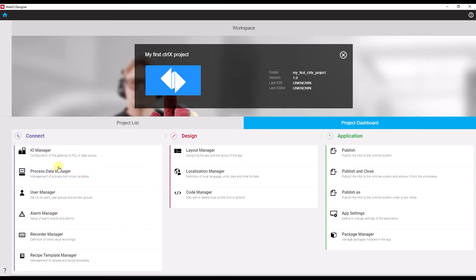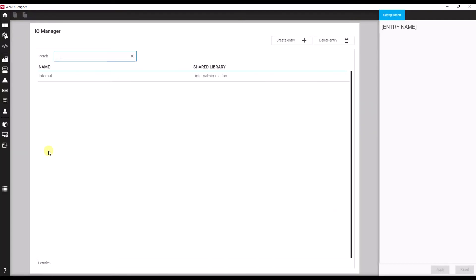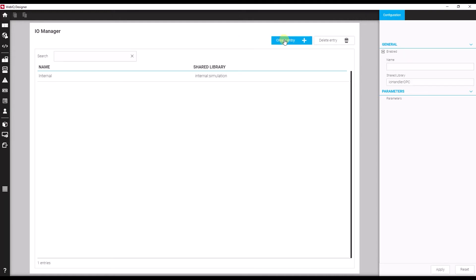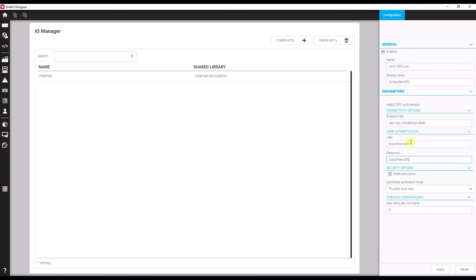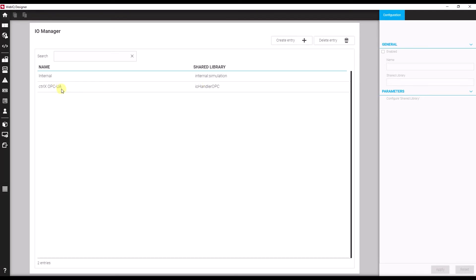We will start with the process data manager — the IO manager — to connect our designer to our OPC UA server. So let's create an entry. We have to provide the endpoint here, using the standard OPC UA account. But of course, in a final application, you should use something more secure. If I apply, it will now try to talk to the OPC UA server.